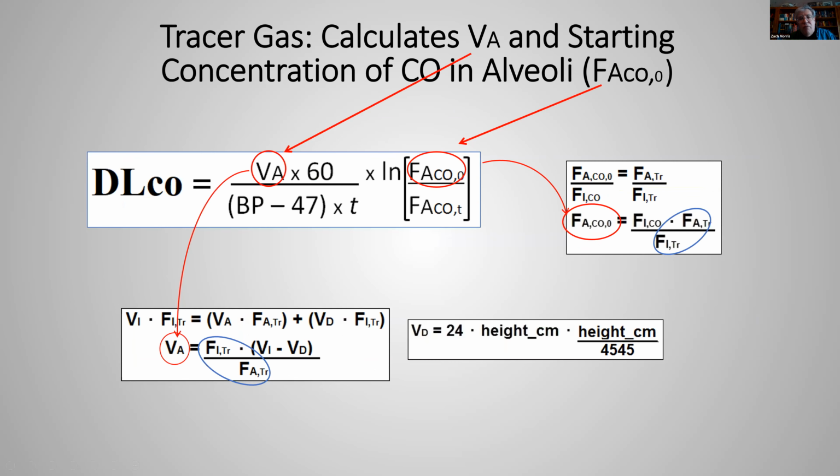Now, all I want to show you on this curve here is how the machine calculates diffusion. This is the equation for it. You use the tracer gas to calculate alveolar volume. And if you look at the guidelines, they actually go through this step-by-step for you, which is kind of neat, okay? But eventually you get the alveolar volume by using the tracer gases.